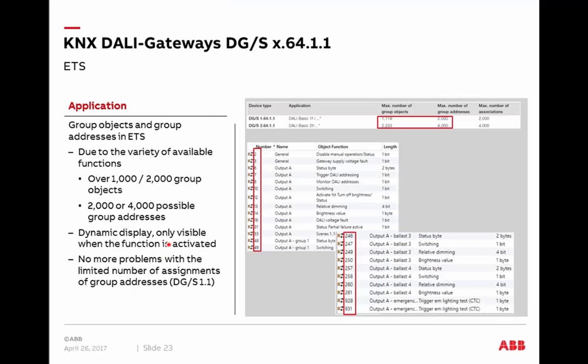The amount of group addresses and communication objects in these new components is remarkable. The one-fold device has over 1,000 possible group objects, resulting in 2,000 possible group addresses that can be assigned. The two-fold device has roughly double. Thanks to the new processor inside, there is practically no limit anymore. This was a challenge with the DG/S 1.1, which had a limit of 255 group addresses — creating many KNX groups could easily reach that limit. That limitation is now completely eliminated with the new gateways.